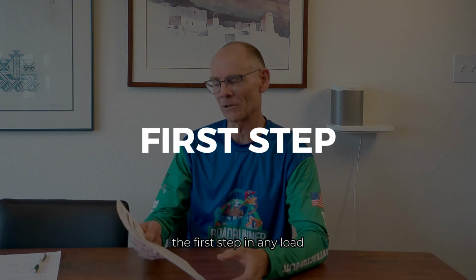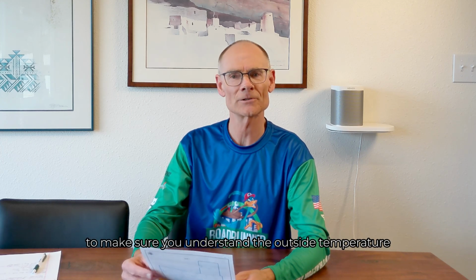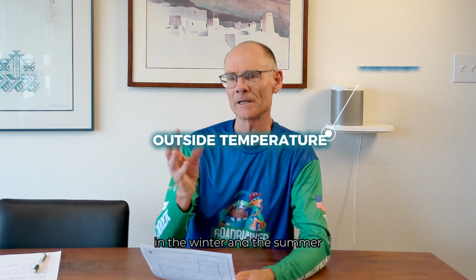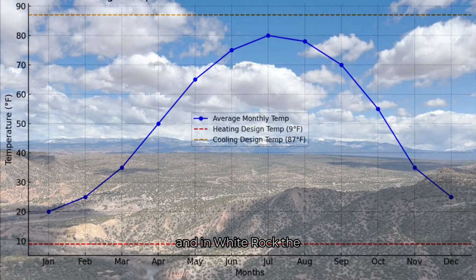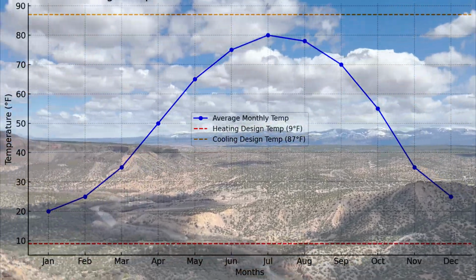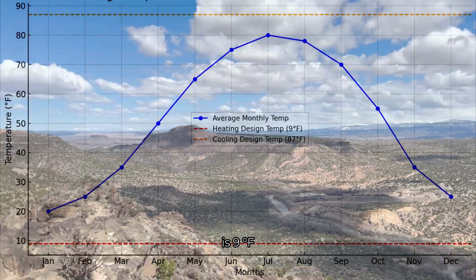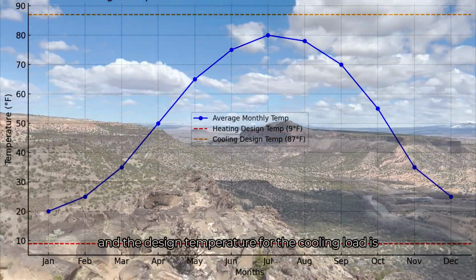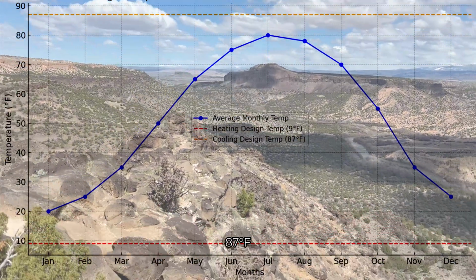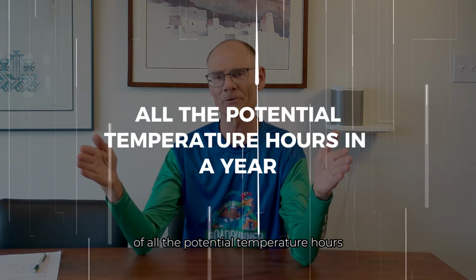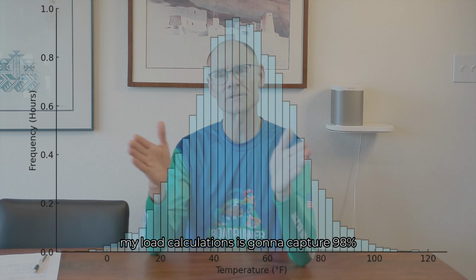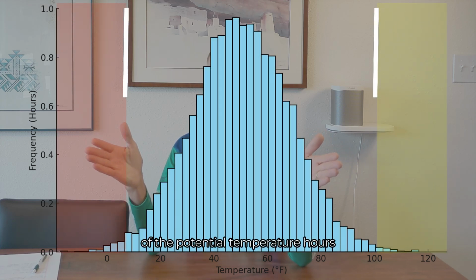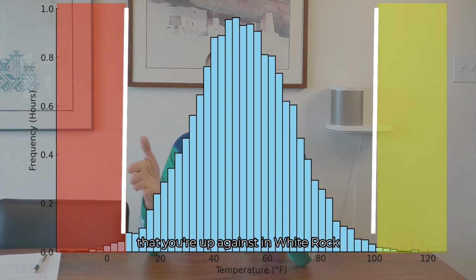The first step in any load calculation is to do the design parameters. You set those to make sure you understand the outside temperature in the winter and the summer. And in White Rock, the design temperature for the heating loads is 9 degrees, and the design temperature for the cooling load is 87 degrees. These two temperatures represent the 1st percentile and the 99th percentile of all the potential temperature hours in a year. My load calculation is going to capture 98% of the potential temperature hours that you're up against in White Rock in this example.